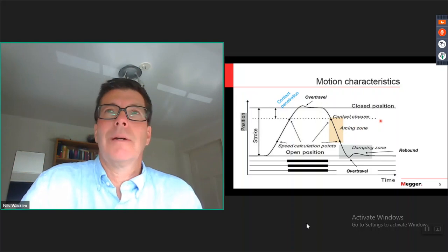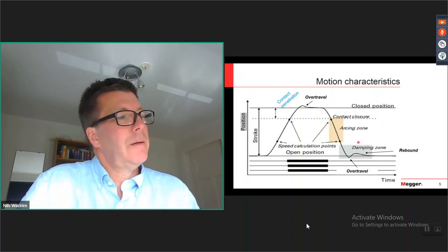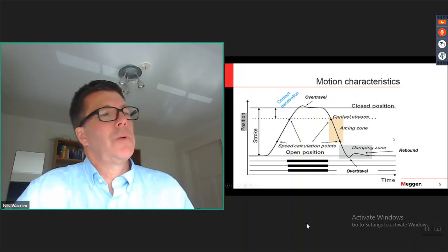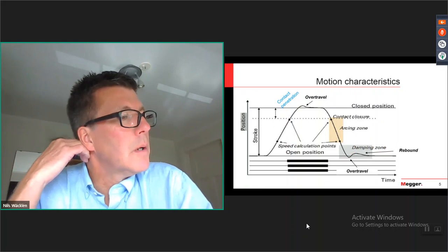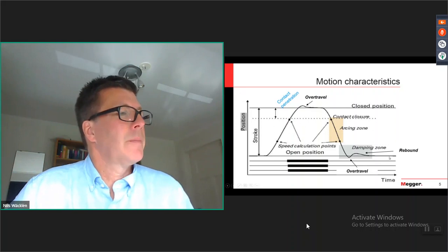It's a little bit less good isolator, so the risk of restriking is bigger than in this situation. But if you have that kind of rebound, there is a serious problem with the breaker.